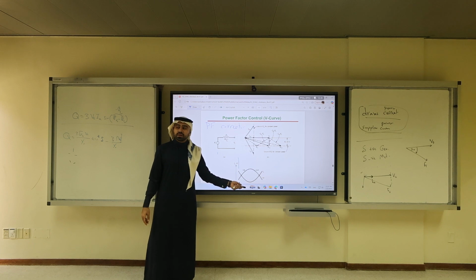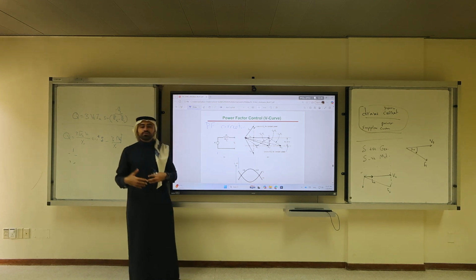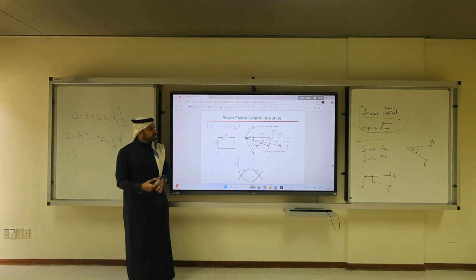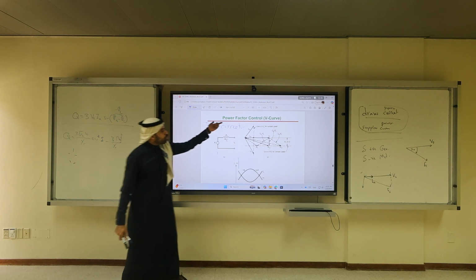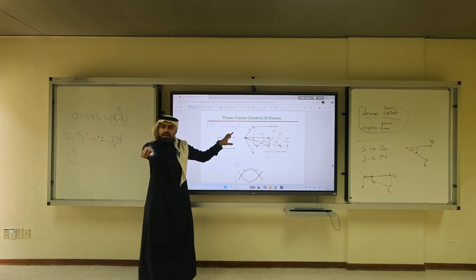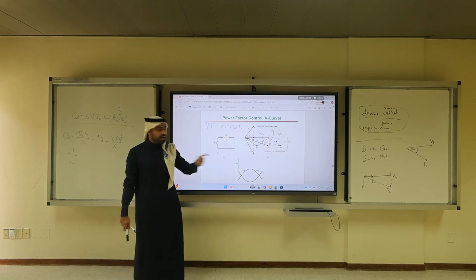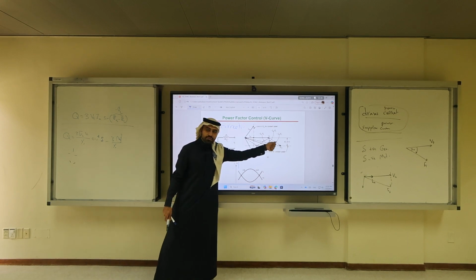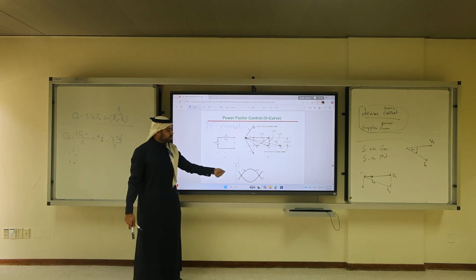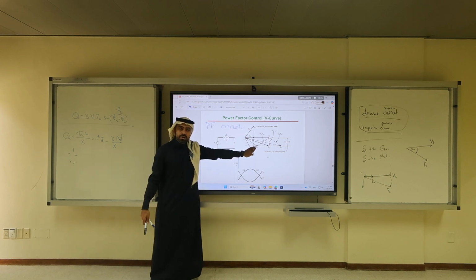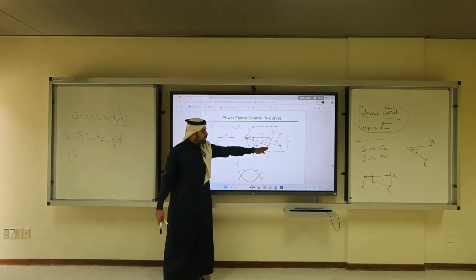Can we use a permanent magnet synchronous motor? No. This is the regular field excited motor. So if you have motors, you can use them to control the power factor of the terminal. That's the right technical way. By changing what? EF. Sometimes I want a lagging, so I go and reduce my field.